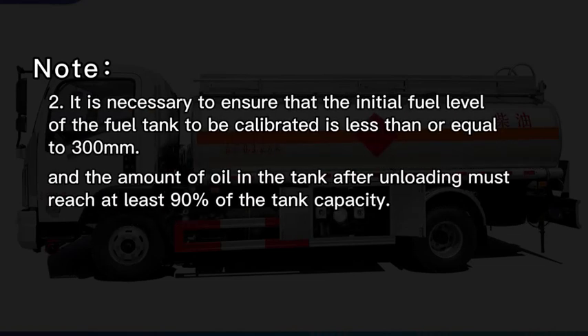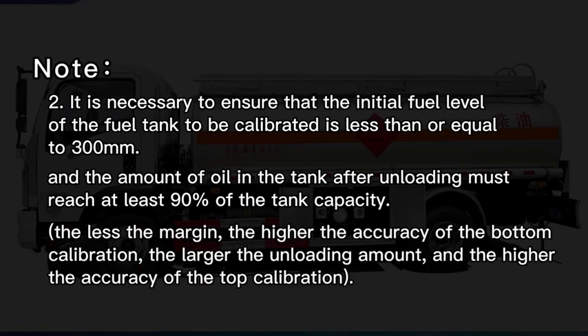2. It is necessary to ensure that the initial fuel level of the fuel tank to be calibrated is less than or equal to 300 mm, and the amount of oil in the tank after unloading must reach at least 90% of the tank capacity. The less the margin, the higher the accuracy of the bottom calibration; the larger the unloading amount, the higher the accuracy of the top calibration.